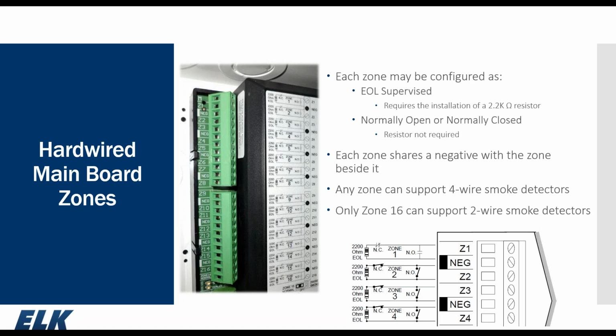Now, there are some devices that require the resistor. Smoke detectors, for instance, is one of them, so you would have to incorporate the resistor with the detector. So giving you that option of not having the resistor, if you can't get it in the location where it does the most good for proper supervision, you do not have to put it at the panel. If it's at the panel, it's not really doing the job it was intended to, and therefore the loop going from the zone to the device could still get shorted, and the panel would not know that that particular device is no longer active. So end-of-line resistors at the sensor, or if that's not a possibility, then you can omit them and configure the zone normally open or normally closed.